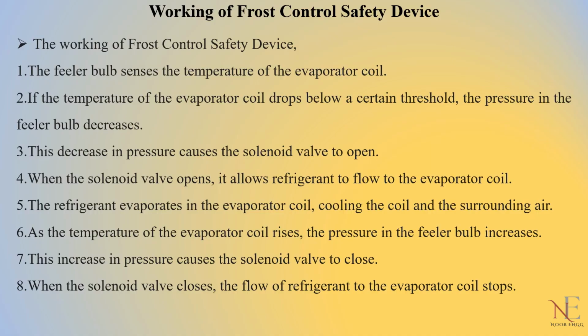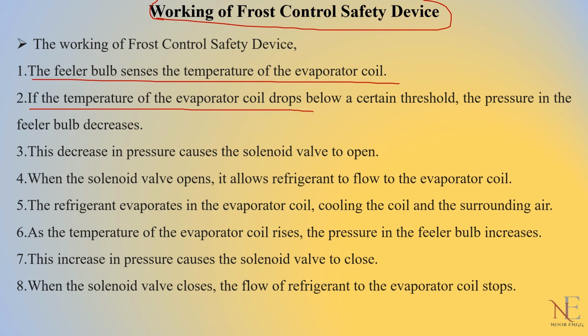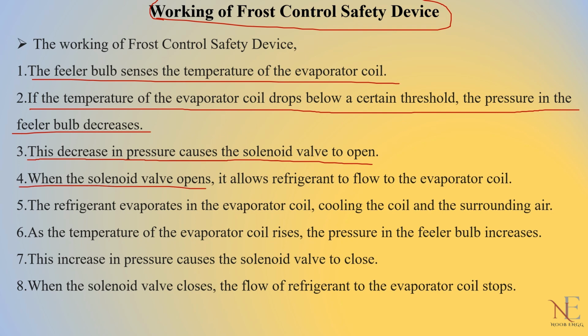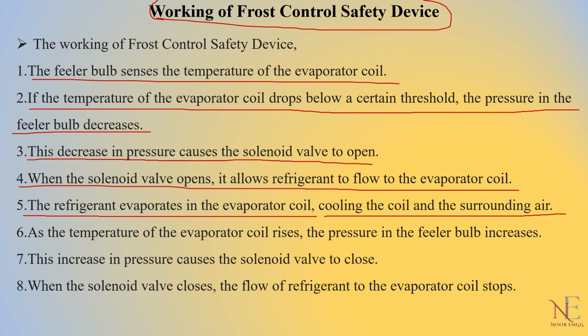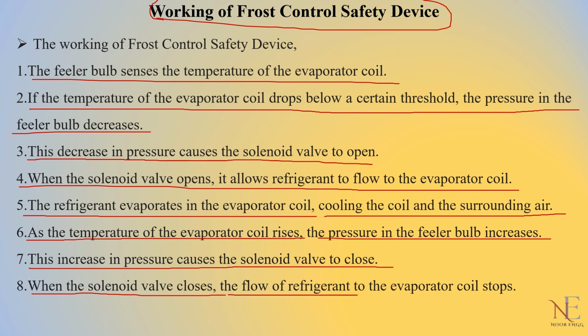Let's see the working here. This is the working of a frost control safety device. The feeler bulb senses the temperature of the evaporator coil. If the temperature of the evaporator coil drops below a certain threshold, the pressure in the feeler bulb decreases. As I discussed, this decrease in pressure causes the solenoid valve to open. When the solenoid opens, it allows refrigerant to flow to the evaporator coil. The refrigerant evaporates in the evaporator coil, cooling the coil and the surrounding area. As the temperature of the evaporator coil rises, the pressure in the feeler bulb increases, and this increase in pressure causes the solenoid valve to close. When the solenoid valve closes, the flow of refrigerant to the evaporator coil stops. As simple as I explained.